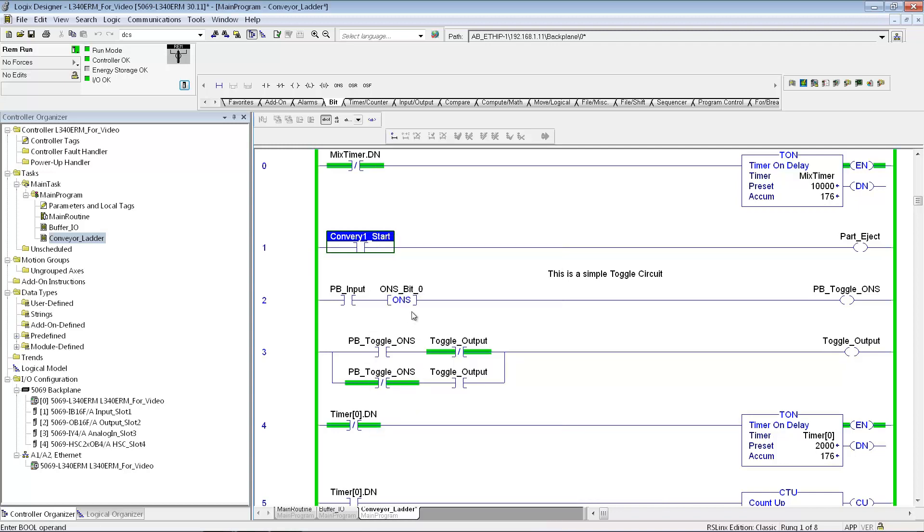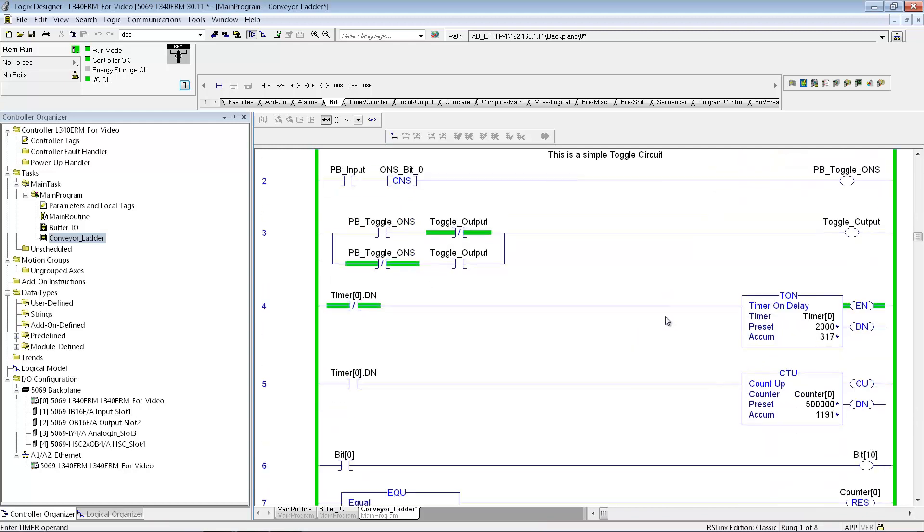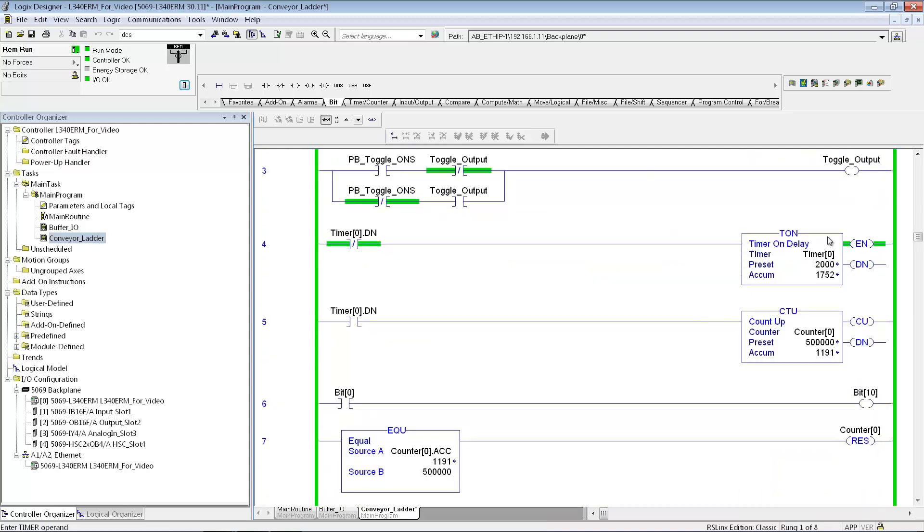And if I want to start this, toggle this bit on, I could force this on. It's actually hooked up to a real world input right now. Then this output would turn on. And you can see how the timer works. It's just a free running timer. It's a 10 second timer. After 10 seconds the done bit goes on. And it recycles the timer.